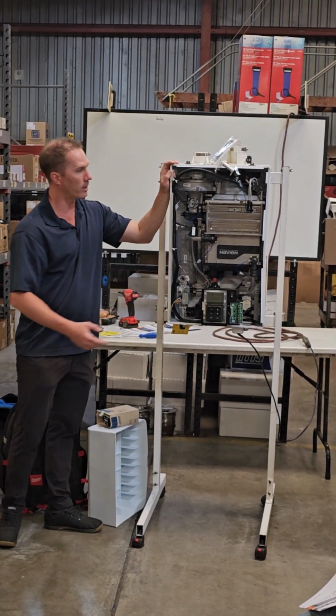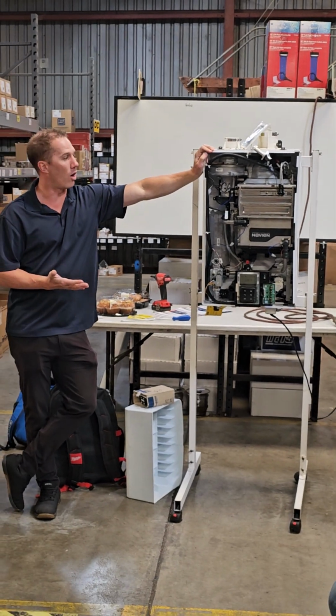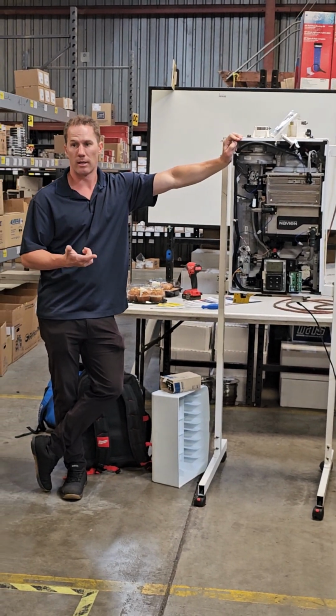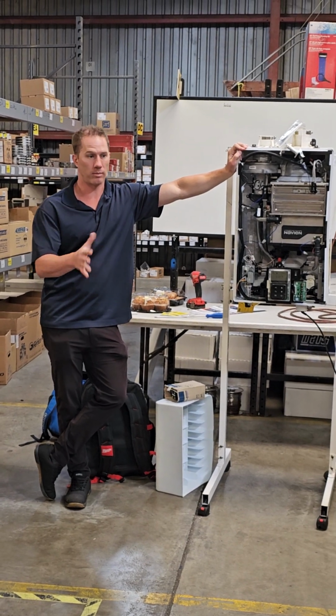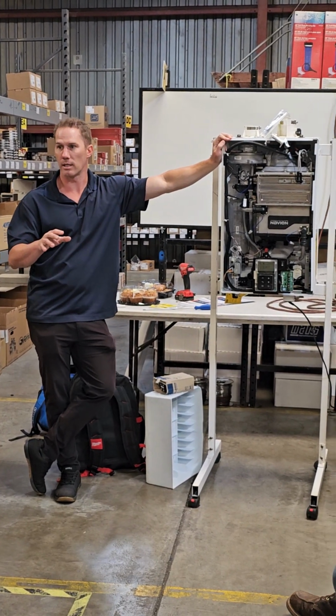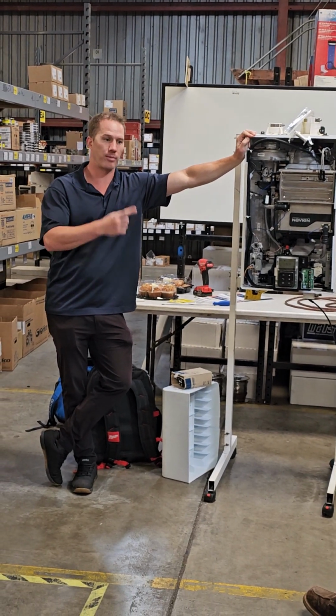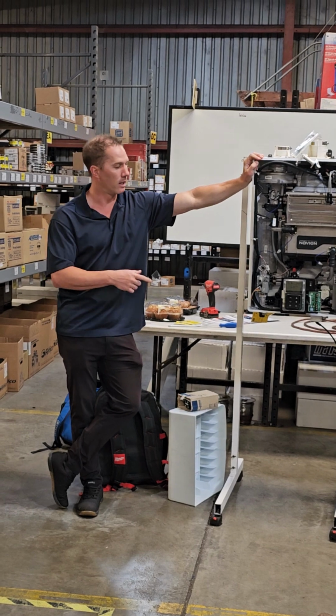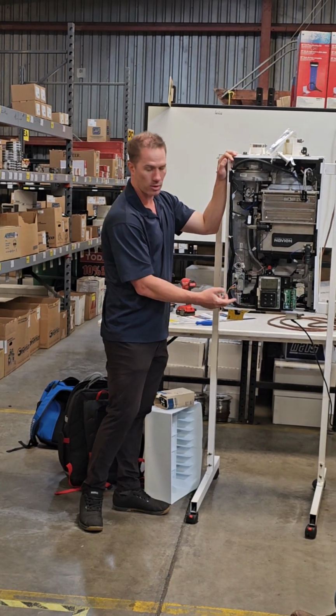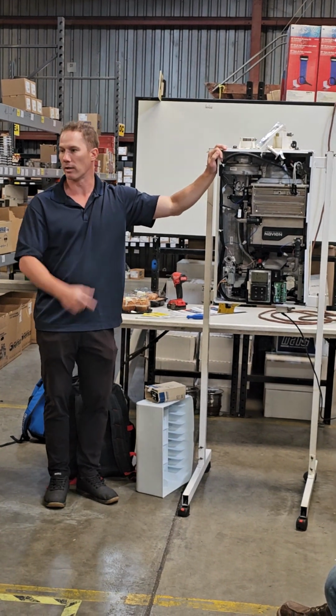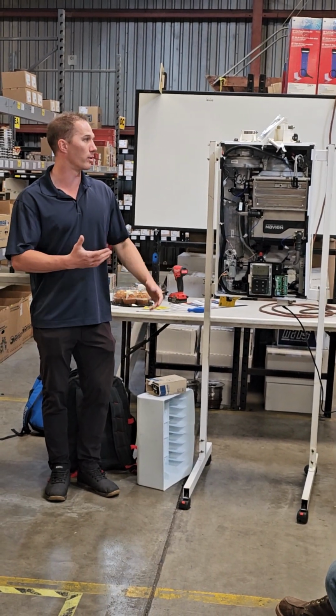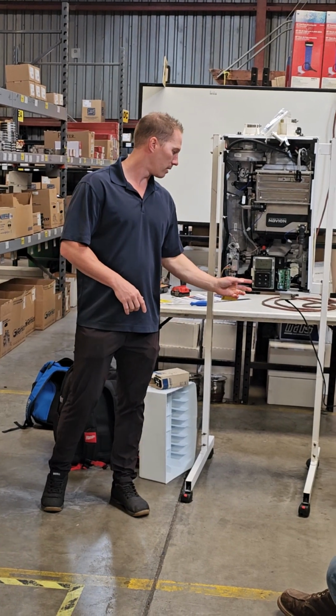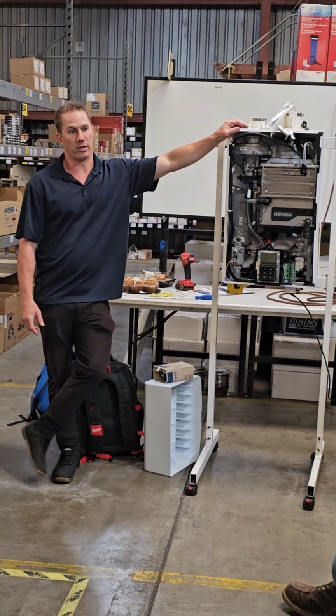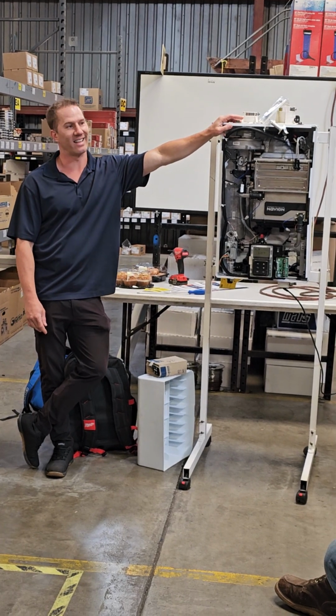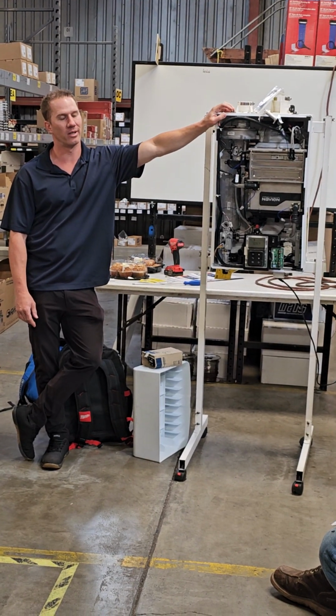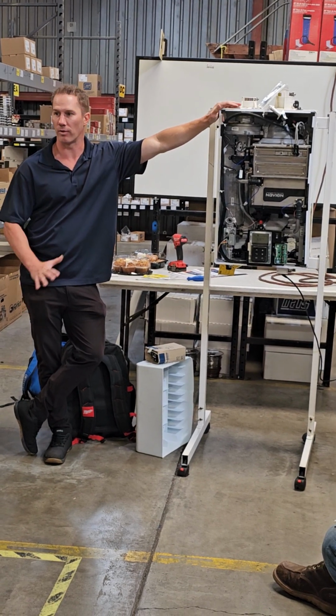So, dip switch number 2 is just temperature lock. I always flip dip switch number 2 on outdoor installs, because when it's outdoor, it's open, and little kids like to press buttons, and they'll go up and hit the plus and minus, turn it up to 140 degrees, turn it down to 85 degrees. But if you flip dip switch number 2, it's a temperature lock. All it does is we can't turn the temperature up and down until you undo dip switch number 2. So any outdoor install, I always do dip switch number 2. Or on any install ever, so the homeowners don't go mess with it all the time. I think that every single install that I've gone to, the temperature's been at least 125 to 140.